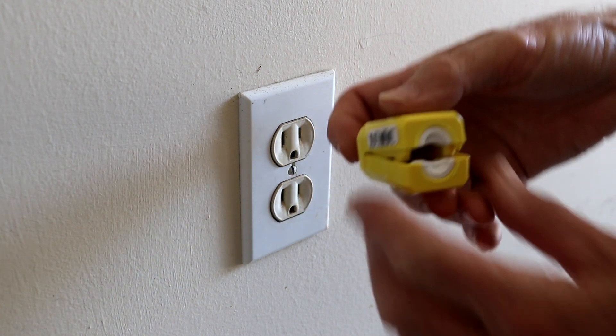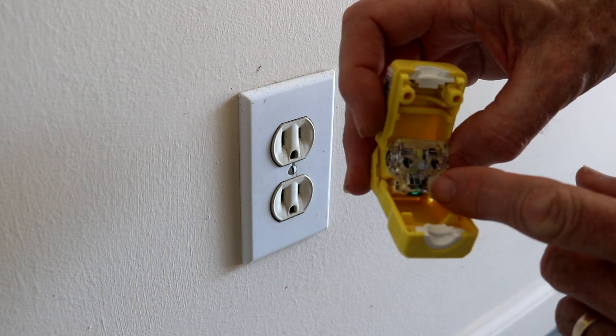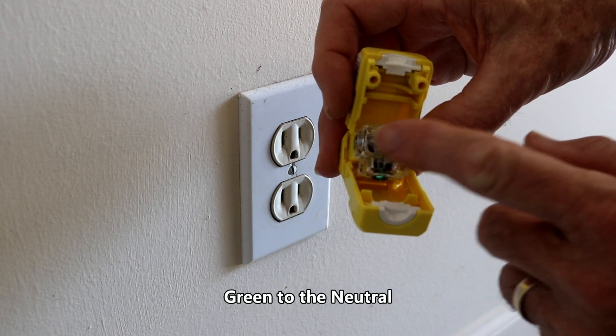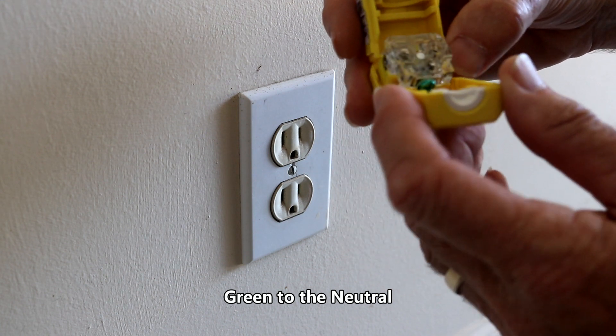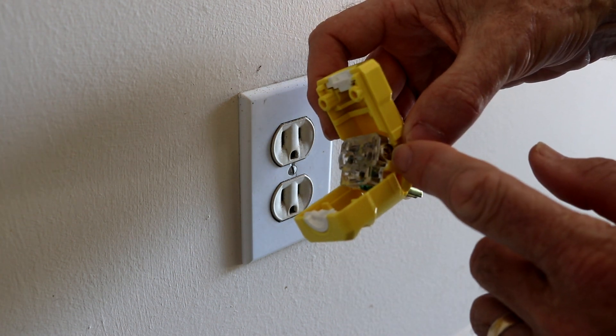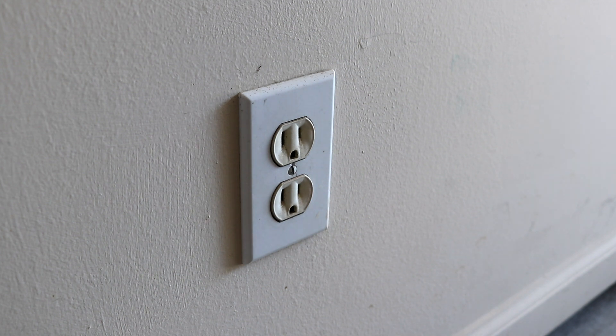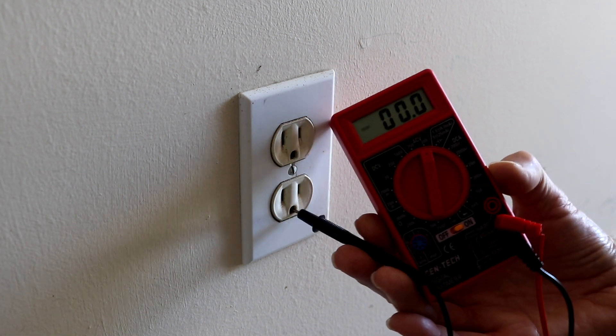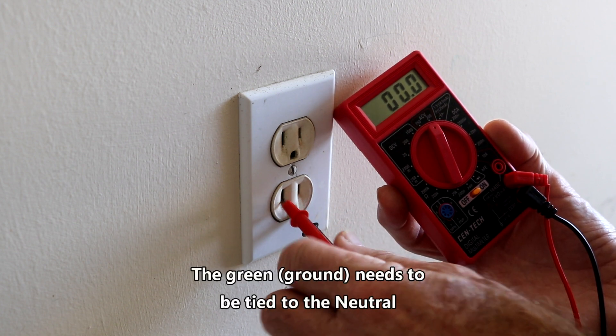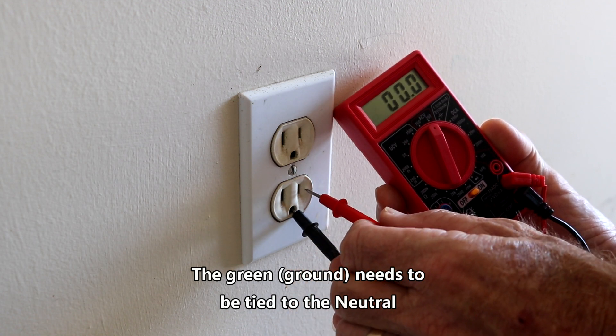The only critical thing is that we make sure we know which wire is which. Green is ground, but we're not sure which one's hot. We need to tie the green to the neutral. It doesn't look like it's color-coded, but theoretically the gold screw should be hot and the silver one is usually neutral. Let's find out for sure because we can't afford to make that mistake. So we know this is hot and this is the neutral.